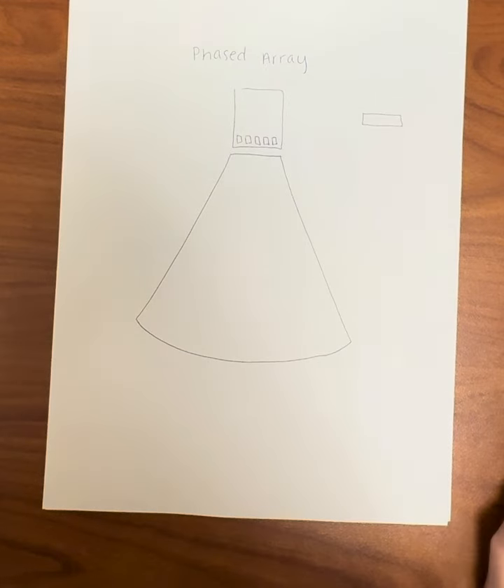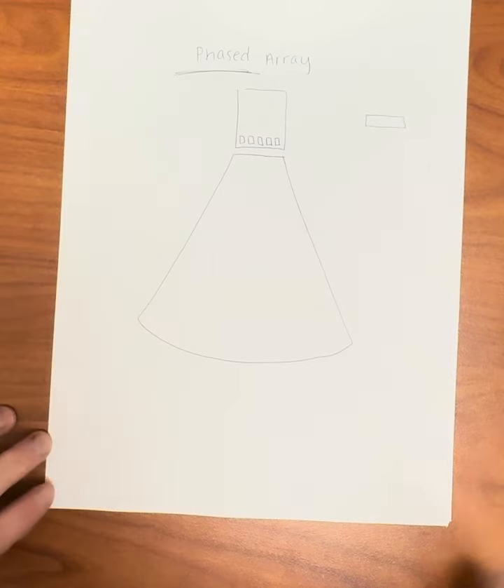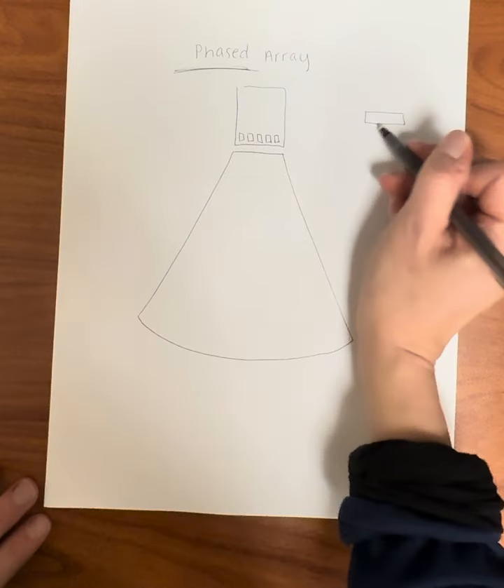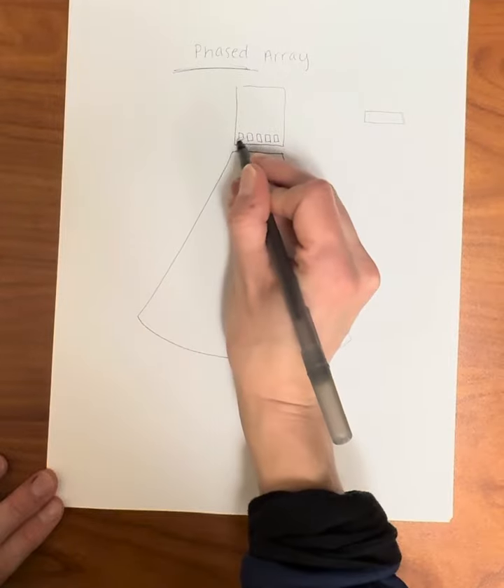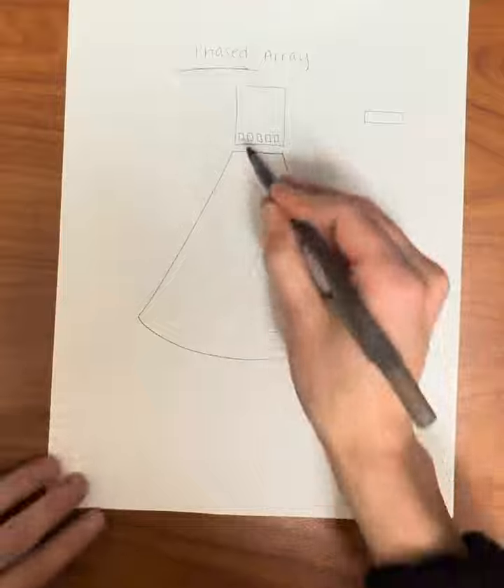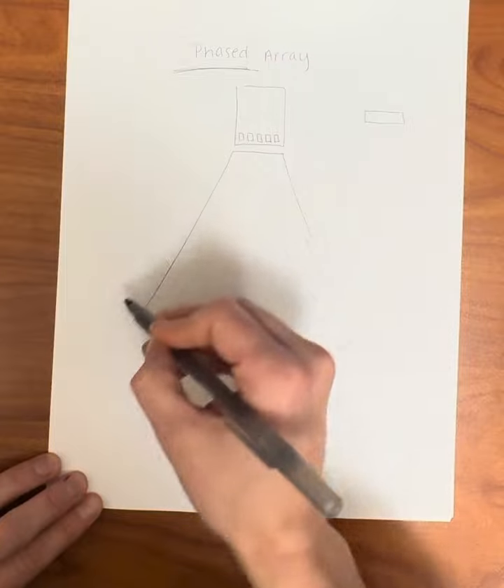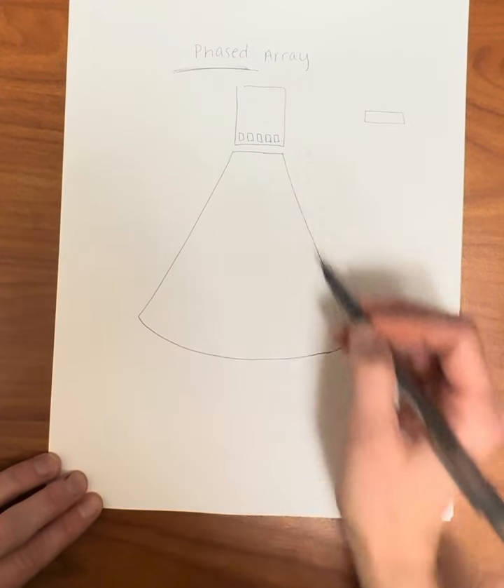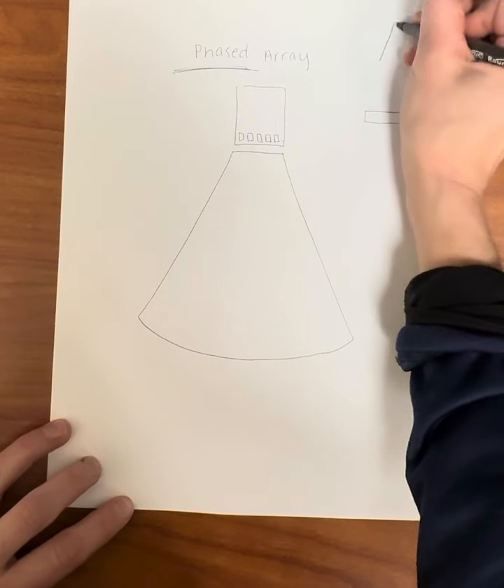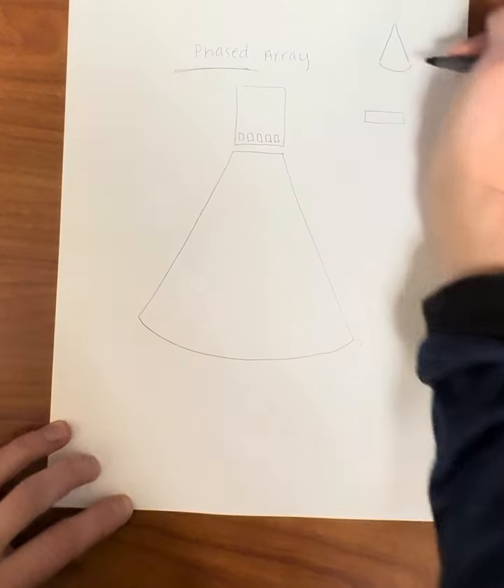Now let's talk about this in terms of our actual transducers. So the most common one that we think about with phasing is the phased array transducer. This used to be the only one that had phasing, right? But now we do have phasing on some of our sequential transducers as well. So this phased array transducer has a rectangular footprint, and the elements are lined up right along the footprint. But this phased array transducer makes either a vector or a sector shape image. So this is a vector shape here. A sector would come out of a common point of origin and look more like that.